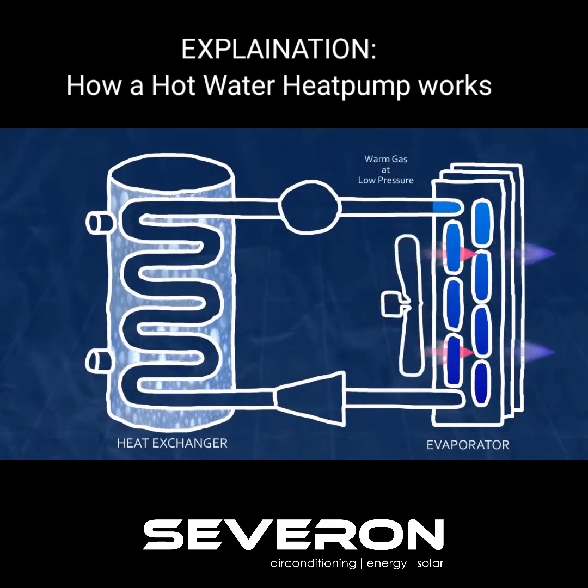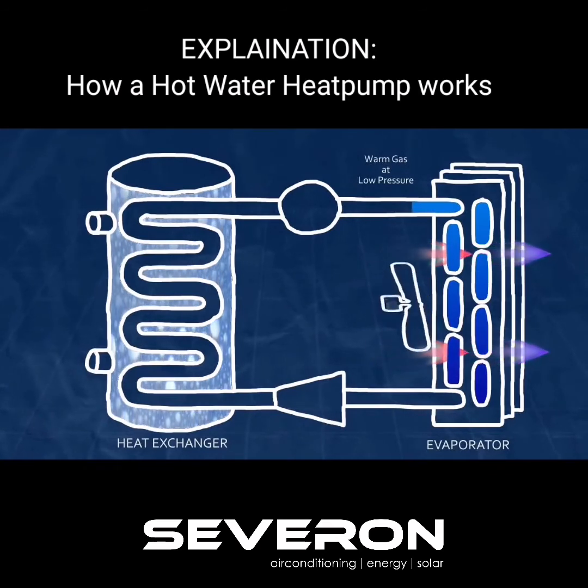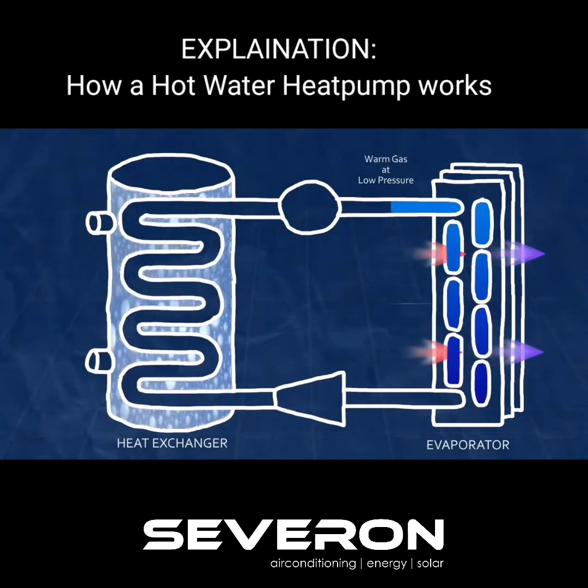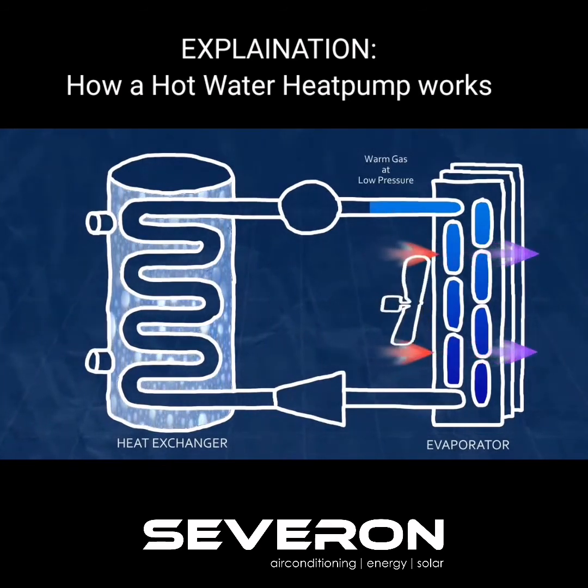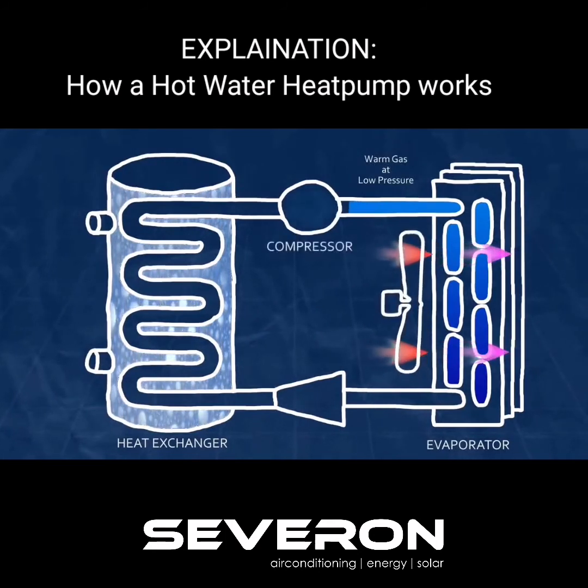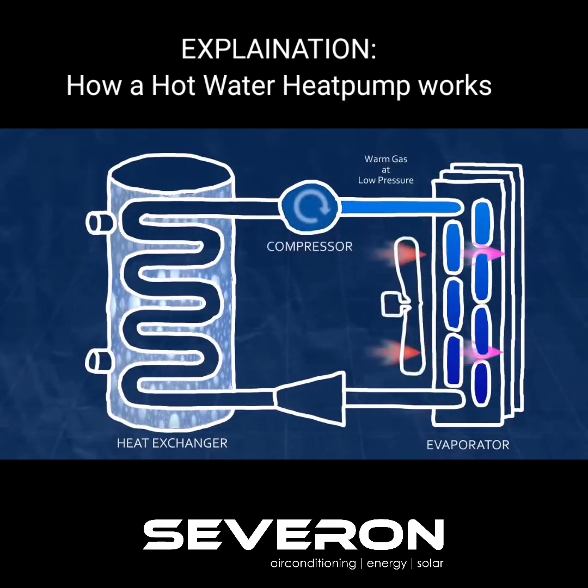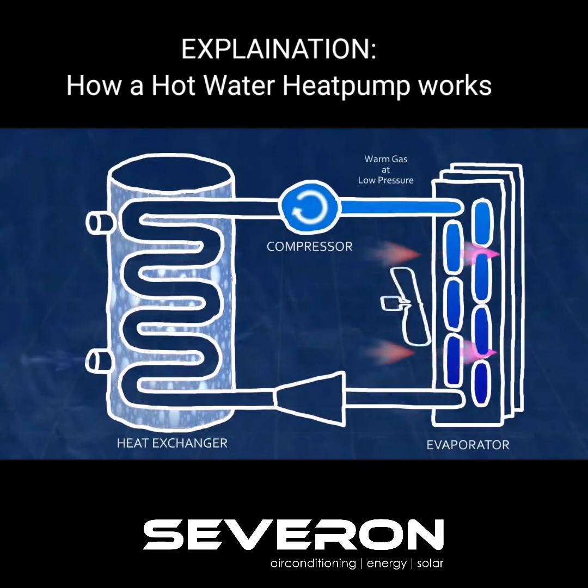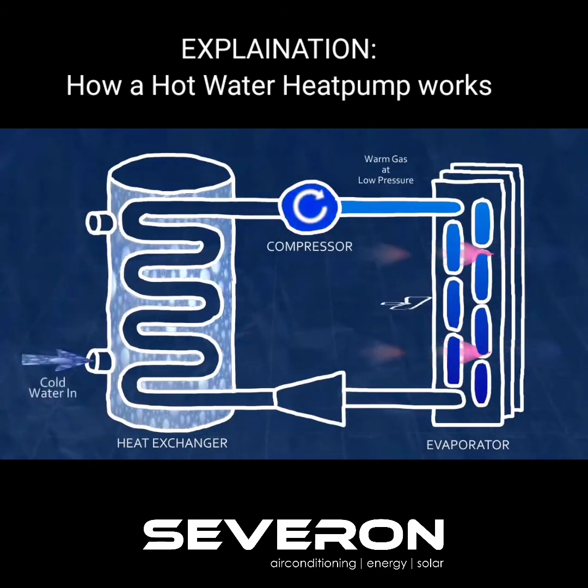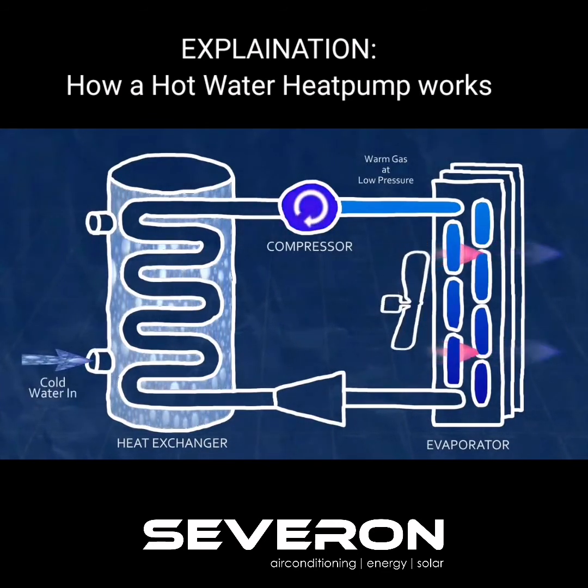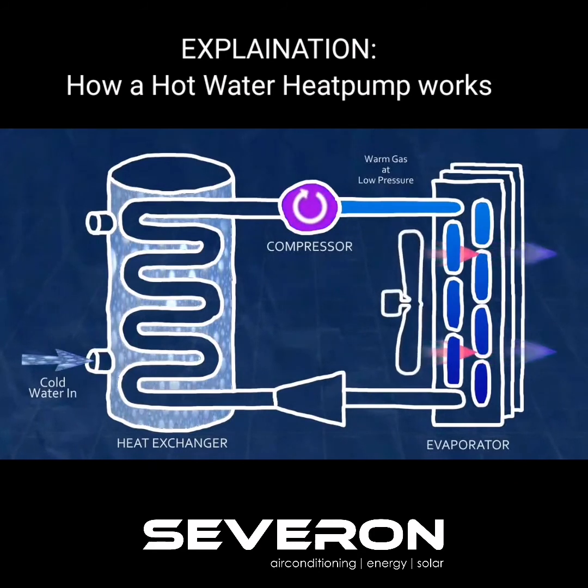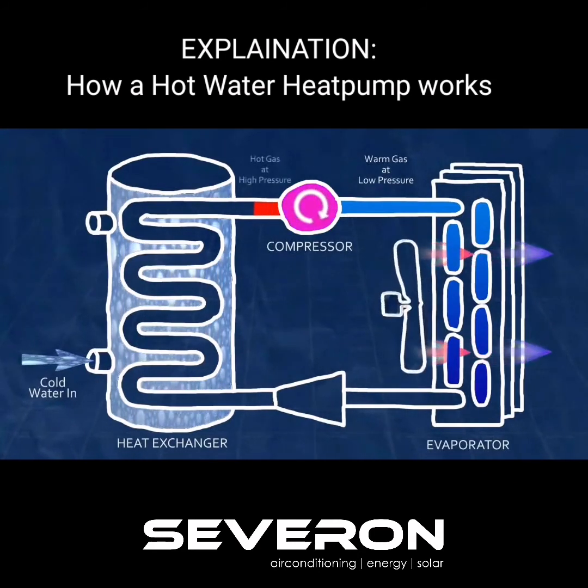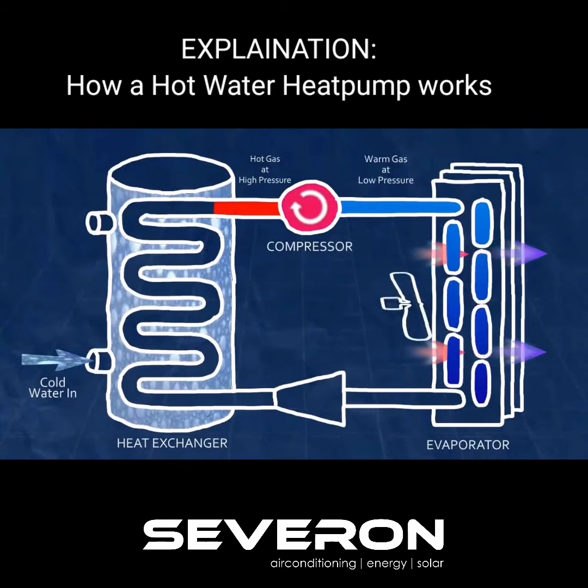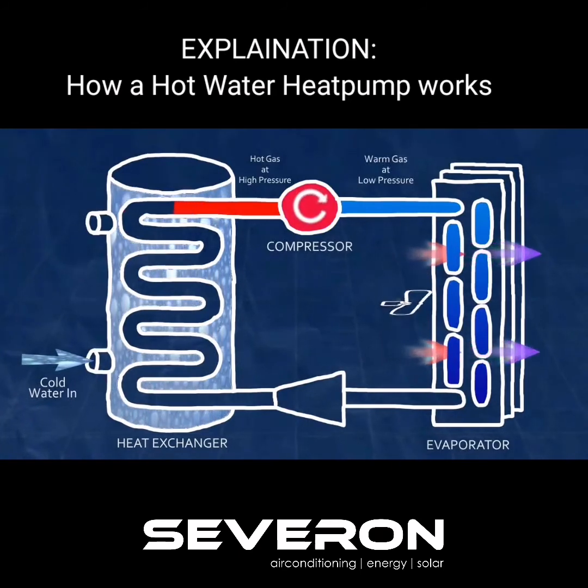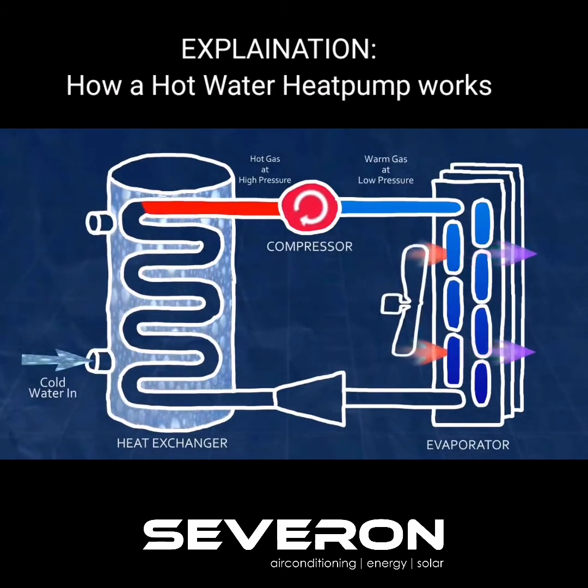The refrigerant is still not hot enough to heat water, however, so that's where the compressor comes in. The compressor raises the pressure of the gas, which also raises its temperature. Once it's hot enough, the heat will flow from the refrigerant to the water. The compressor next forces the now high-temperature, high-pressure gas further along the cycle into another heat exchanger called the condenser.